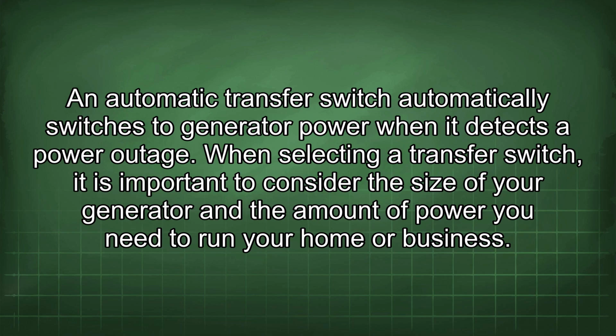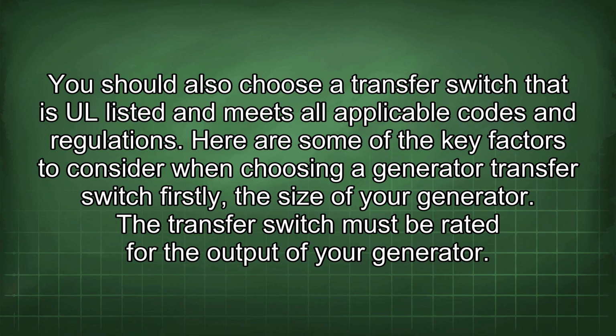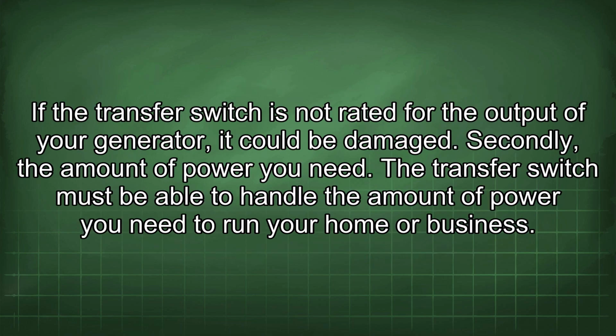When selecting a transfer switch, it is important to consider the size of your generator and the amount of power you need to run your home or business. You should also choose a transfer switch that is UL listed and meets all applicable codes and regulations. Here are some of the key factors to consider when choosing a generator transfer switch. Firstly, the size of your generator. The transfer switch must be rated for the output of your generator. If the transfer switch is not rated for the output of your generator, it could be damaged.